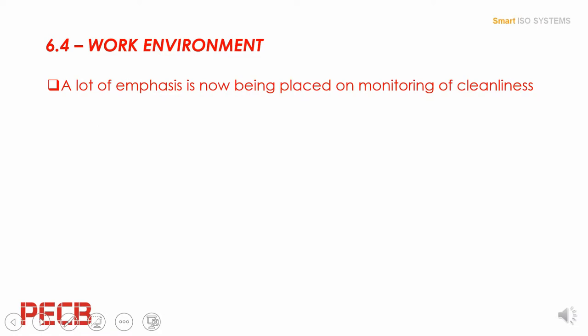The last part under section 6 deals with the work environment. A lot of stress has been placed on cleanliness and monitoring within clean rooms and manufacturing areas that deal with sterilised products, to ensure that monitoring for particles that could have an adverse effect on the product is carried out. They reference ISO 14644, the standard used for controlled environments, as guidance for medical device companies to use in managing clean rooms.